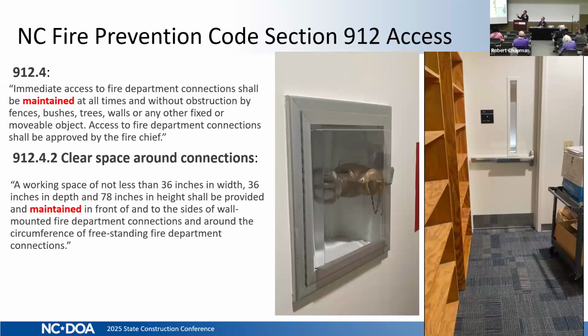So here we have clearances around connections. This time it's a standpipe system for a sprinkler system. These, along with that past slide and this connection, they're typically easy to maintain clearances, right? We have 3 feet in front of it because they're placed in locations where people walk. Usually it's in corridors or something like that, but it's not always the case.